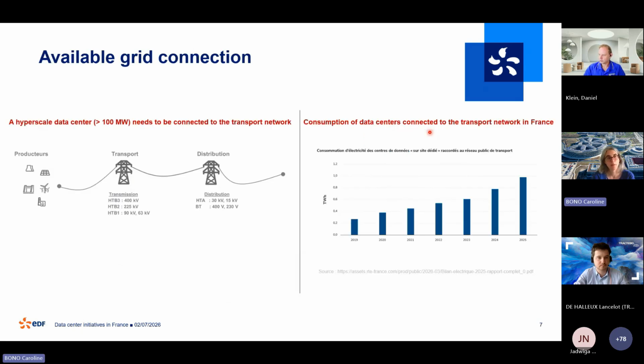And so once you have the power and decarbonized power, you need to be able to connect to the grid. If you have a hyperscale data center, over 100 megawatts, you need to be connected to the transport network. For data centers between 100 and 400 megawatts, you could connect to the 225 kilovolts. After 400, you need to be connected to the 400 kilovolts, the network you saw on the map a couple of slides ago.